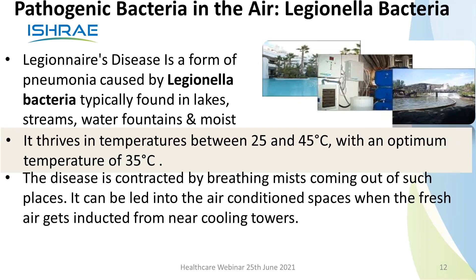It can be led into the air-conditioned spaces through fresh air, which gets inducted from near the cooling towers. So if you're not very careful where the fresh air is coming from for your AHUs, and it is coming from near the cooling towers, there is a very good possibility that you might get in the Legionella bacteria.